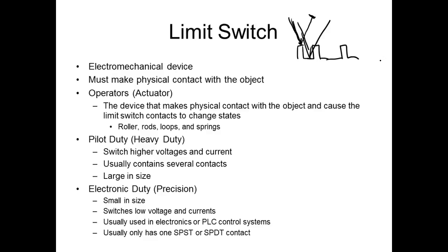I don't think I have any electronic duty limit switches in my bag, but I got some I can bring. But all of y'all had motor control. One of the labs that you did in motor control was with a limit switch. So that thing you see sticking out, of course, that's the operator. This is a heavy duty or what we call a pilot duty. These guys right here are designed to run loads. So the contacts are going to be big. They can handle quite a bit of current. So what a heavy duty or pilot duty limit switch will allow us to do is actually run loads.